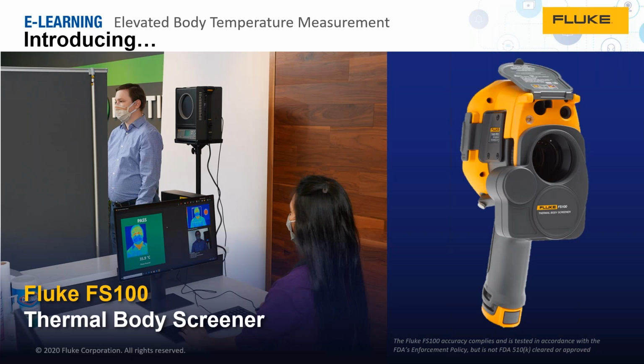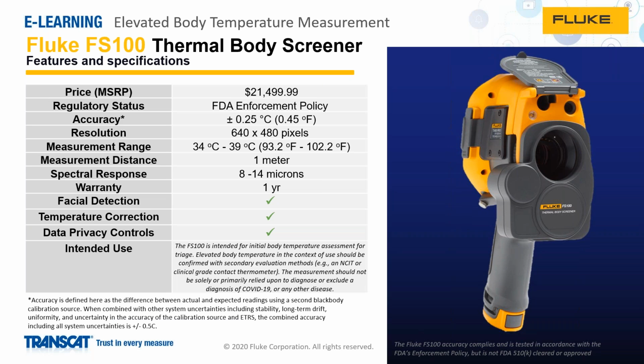And then we'll talk about our other product that we've come out with, which is the Fluke FS100 thermal body screening system. So, under regulatory, we come in under the FDA's enforcement policy, as we've talked about, and that's what we do with the 67 Max as well. The accuracy, as defined below, you can look at the asterisk there, as the difference between the actual and expected readings using a secondary black body or ETRS calibration source is 0.25 C, 0.45 degrees F.